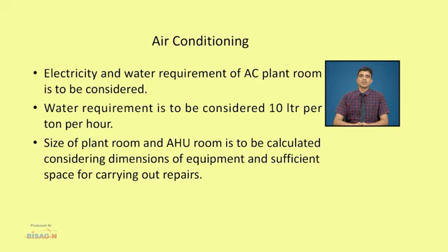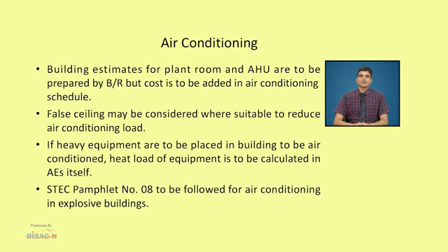Electricity and water requirement of the AC plant room is to be considered. Water requirement is to be considered at 10 liters per ton per hour. Size of the plant room and AHU room is to be calculated considering dimensions of equipment and sufficient space for carrying out repairs. Building estimates for plant room and AHUs are to be prepared by B&R, but the cost is to be added in the air conditioning schedule.